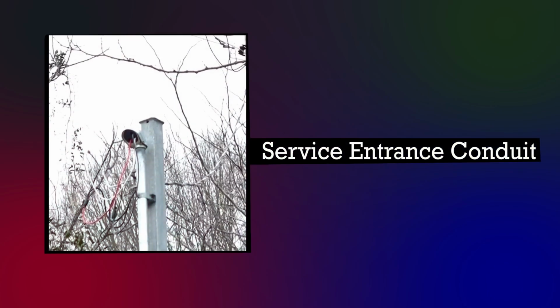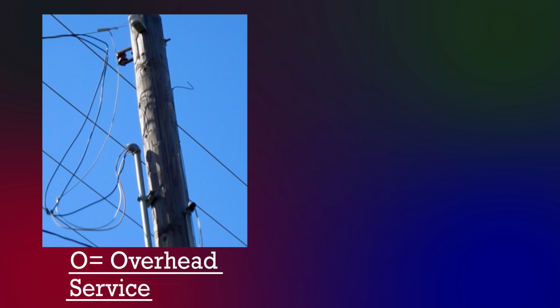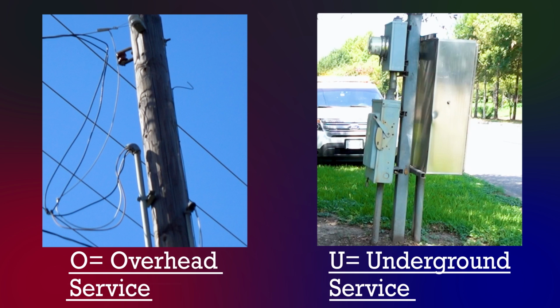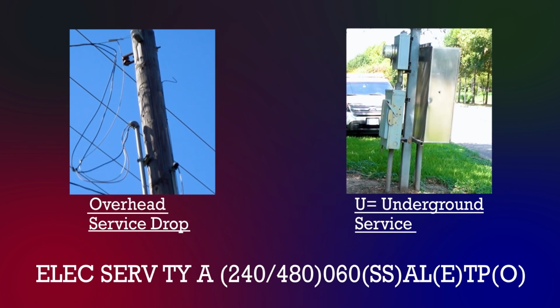The rigid metal conduit from the top of the service to the weatherhead is called the service entrance conduit, or riser. These items will only be used when the service descriptive code calls for an overhead service and is designated with an O. When the conductors connecting to the utility transformer are to be routed underground, the descriptive code uses the letter U. Underground service conductors are called the service lateral. Some electrical services are connected to the overhead service drop conductors, designated by the letter O in the service's descriptive code, while others are connected to an underground service lateral, designated by the letter U.